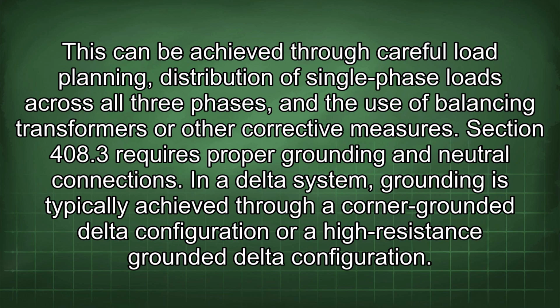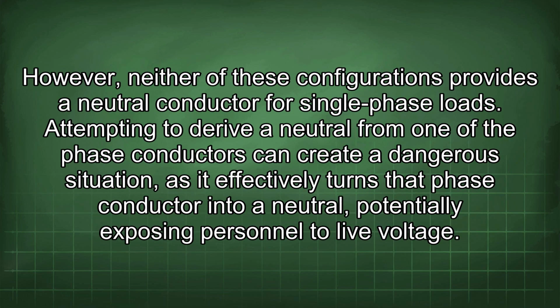Section 408.3 requires proper grounding and neutral connections. In a delta system, grounding is typically achieved through a corner grounded delta configuration or a high resistance grounded delta configuration. However, neither of these configurations provides a neutral conductor for single-phase loads. Attempting to derive a neutral from one of the phase conductors can create a dangerous situation, as it effectively turns that phase conductor into neutral, potentially exposing personnel to live voltage.